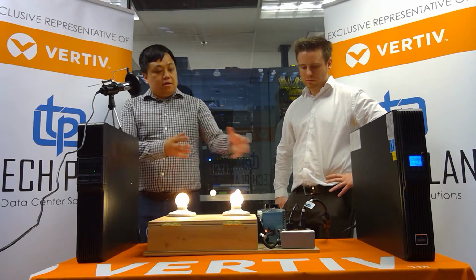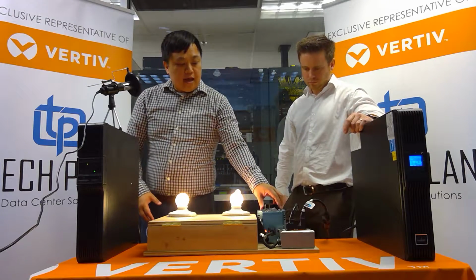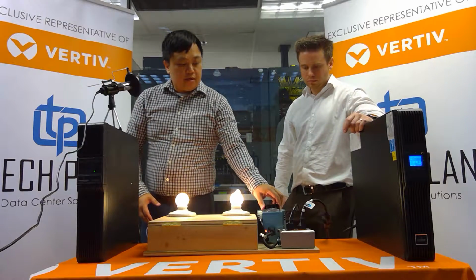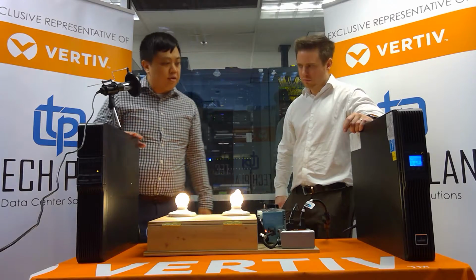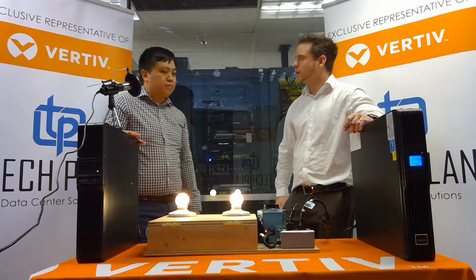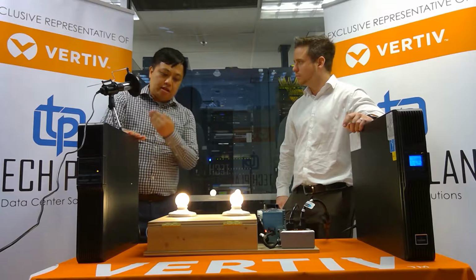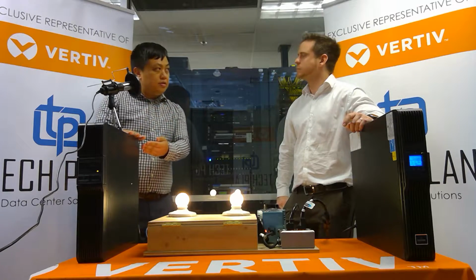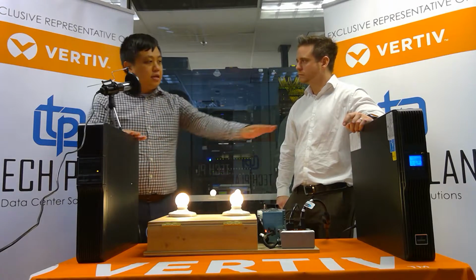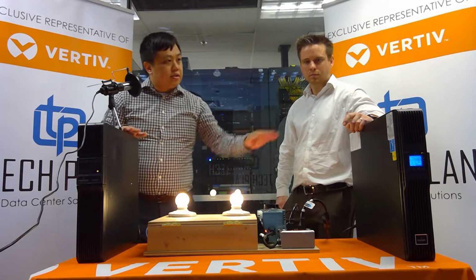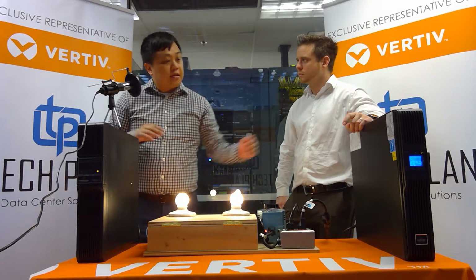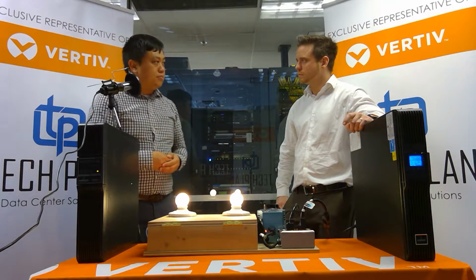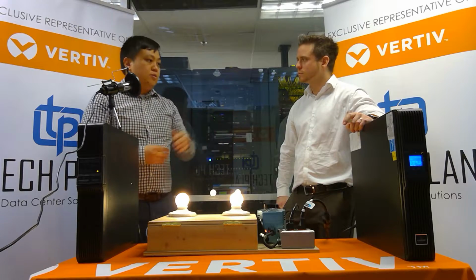Okay. So I'm going to go ahead and simulate a sag. We're down to about 90 volts. And we heard a beep here because this is now on battery, because it has a momentary duty inverter, where this is a continuous duty inverter. So this is actually still running on utility, but because it's double conversion, we can buffer that quite a bit more. Let's see what that limit is.